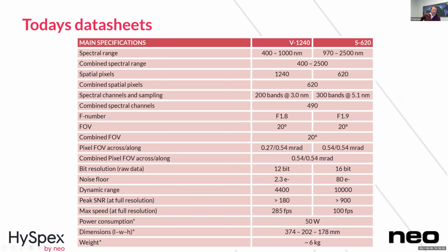Yeah, so here I start with our datasheet as a good example of a bad example. Basically, it's a datasheet. This is how all the suppliers today are presenting their cameras. And where we are presenting the spectral range, number of pixels, spatial pixels, number of bands, F number, field of view, bit resolution, noise floor, dynamic range, and so on, and the peak SNR. But actually, this datasheet doesn't tell you anything about how good your optical system is on a pixel level. It just tells you about the top level, how many spatial, how many bands. And I will dig a bit deeper into that.